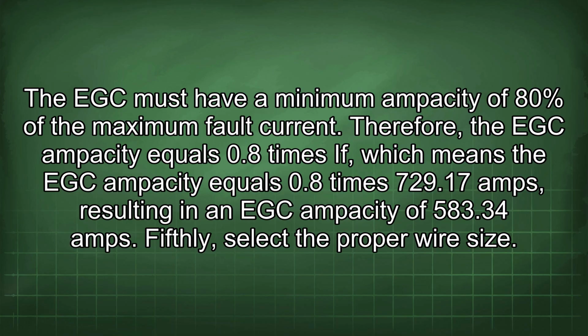The EGC must have a minimum ampacity of 80% of the maximum fault current. Therefore, the EGC ampacity equals 0.8 times If, which means the EGC ampacity equals 0.8 times 729.17 amps, resulting in an EGC ampacity of 583.34 amps. Fifthly, select the proper wire size.